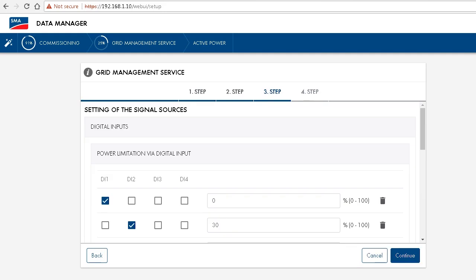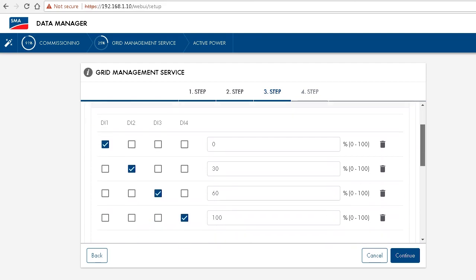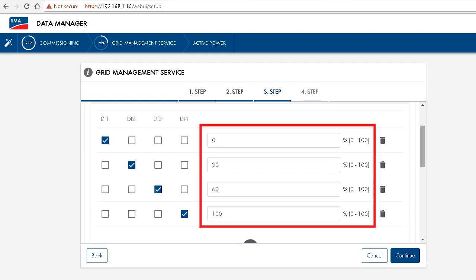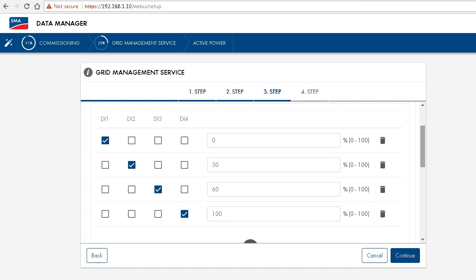We are then able to configure these digital inputs, more precisely to which limits the data manager will translate the digital inputs. But normally the default configuration, in this case 0, 30, 60 and 100 percent, are already in accordance with the grid operator's requirements.